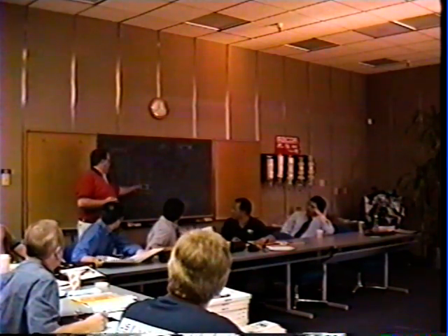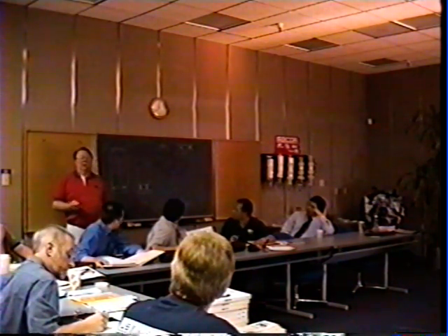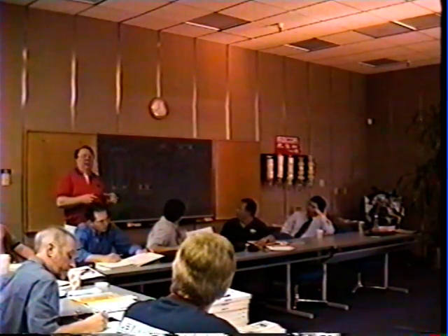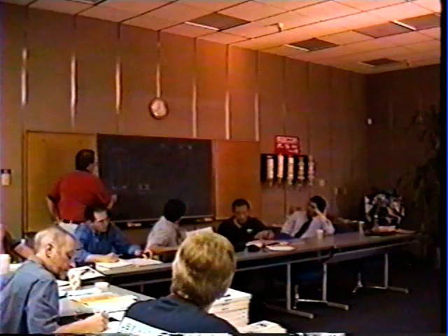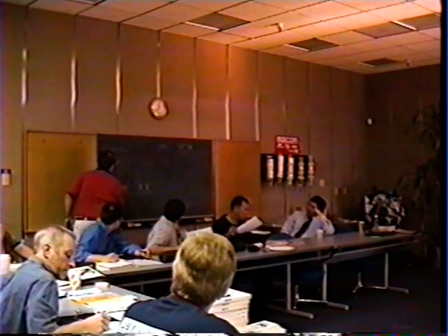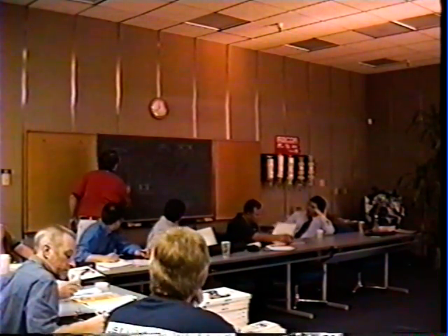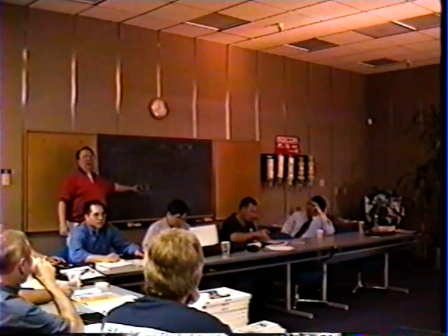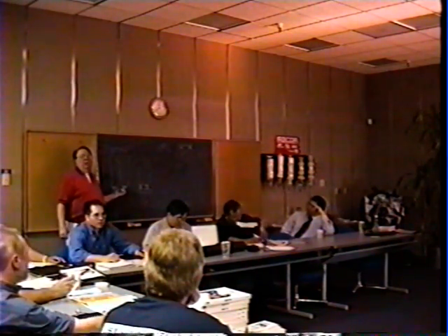Which one is going to give a more positive sealing? Right here. Not the thread. The reason they like these are on some of our longer elements. If you're dropping a 56-inch element into a vessel, you might not get your gasket directly on the knife edge. So maybe it'll slide over a little bit. So on some of the longer elements, they like to go to a thread base rather than a double open end.